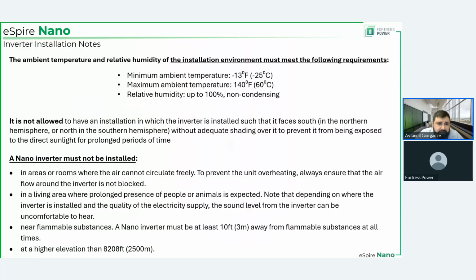We mentioned the tools. We must also talk about where you install it with these tools. So the inverter may be secured onto the battery enclosure, or it may be secured onto some other random wall. It doesn't matter. The inverter is outside, right? And this is not an inverter that has its own separate enclosure, which is climate controlled. No, that's not the case. It's just an air-cooled hybrid inverter.